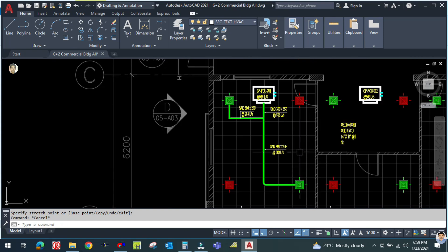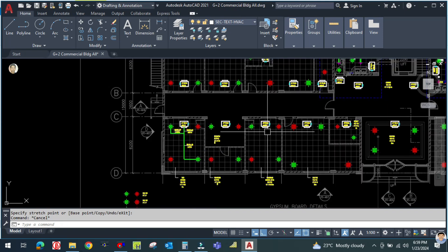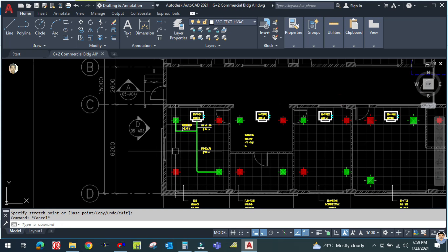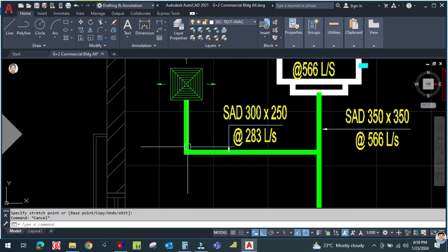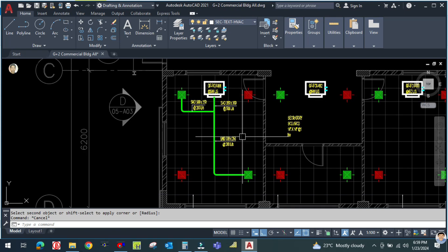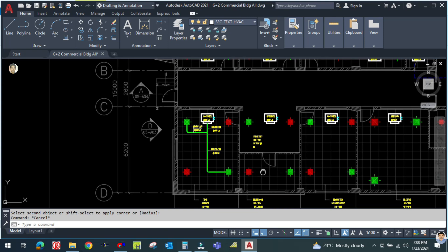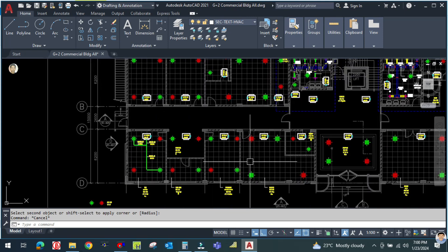I hope you learned how to design and size the duct using the equal friction method in real practice. First we create all the ducting with a single line drawing diagram, then we create the shop drawing using the fillet command. Similarly, we have to design all the ducts for all the spaces. In the next tutorial we will continue with duct designing for other spaces. Thank you for watching.